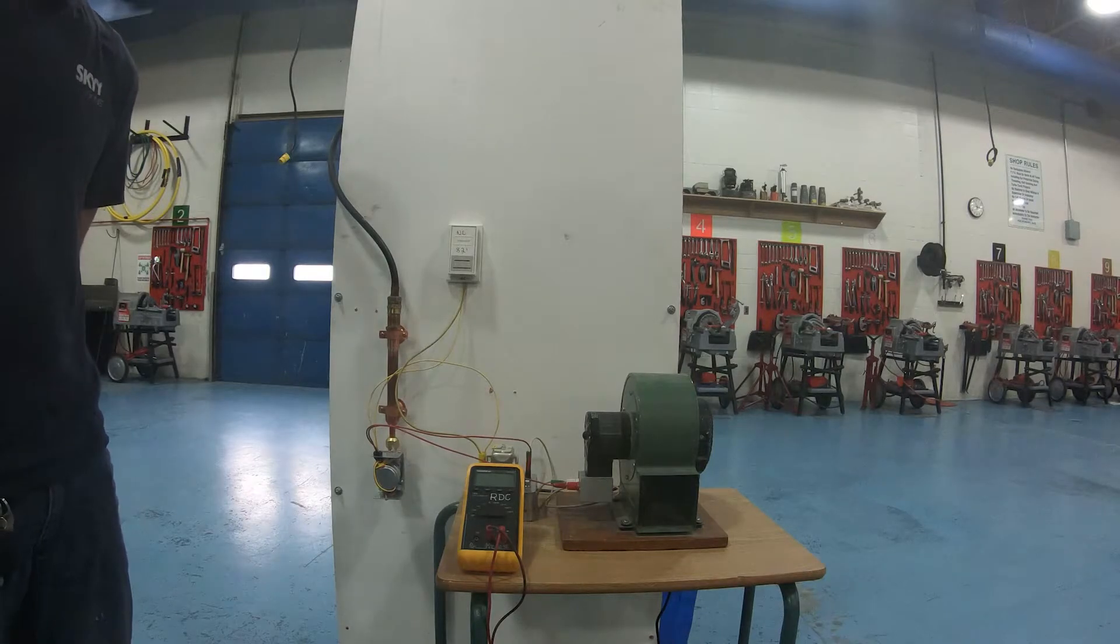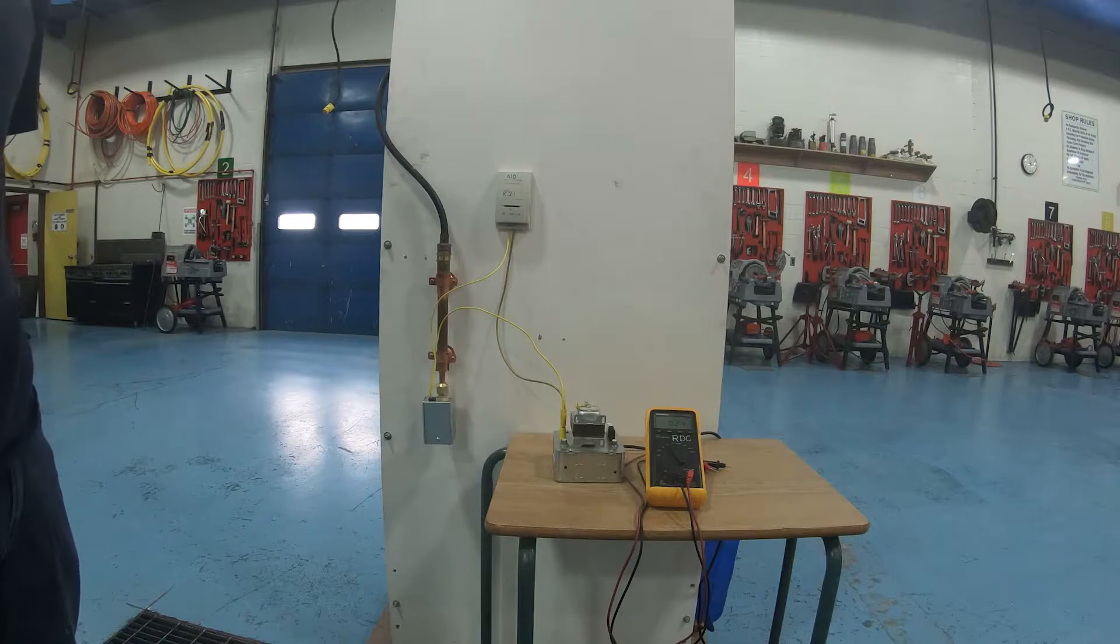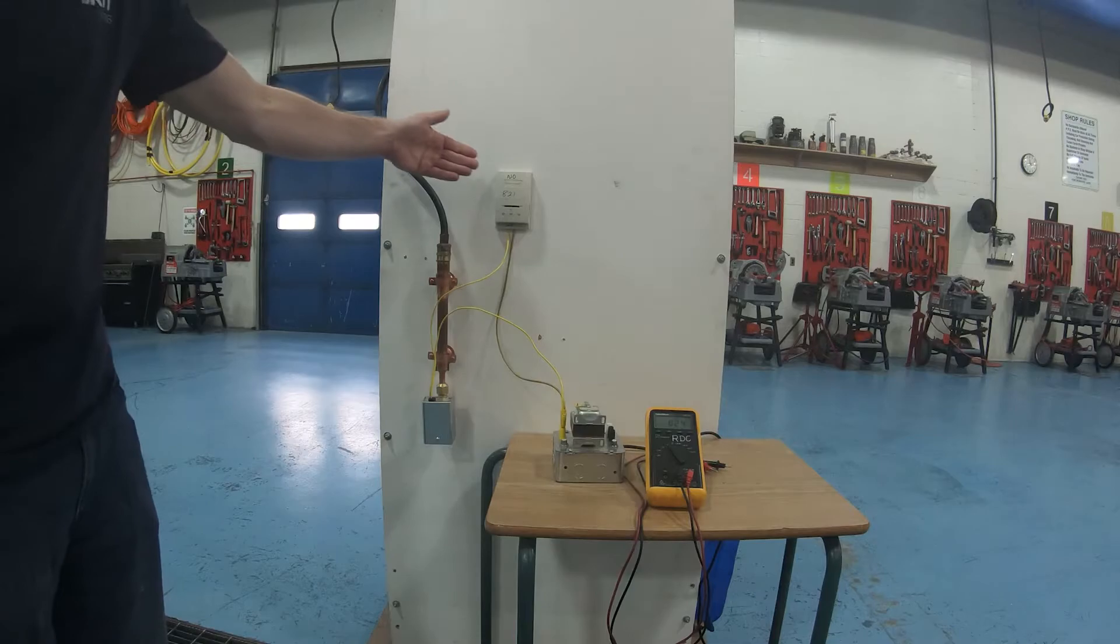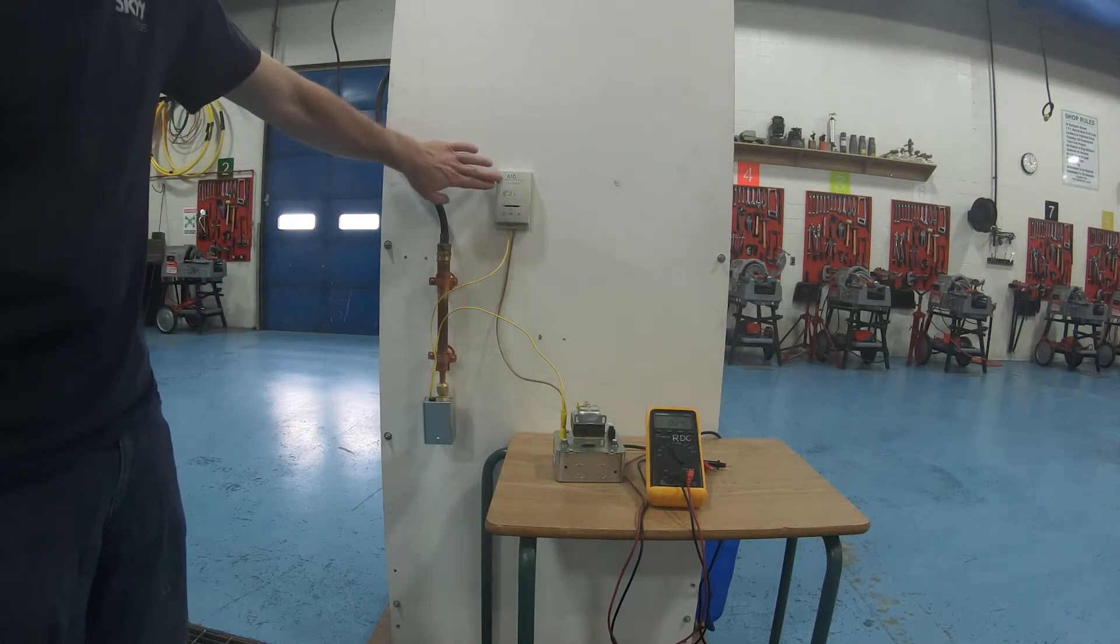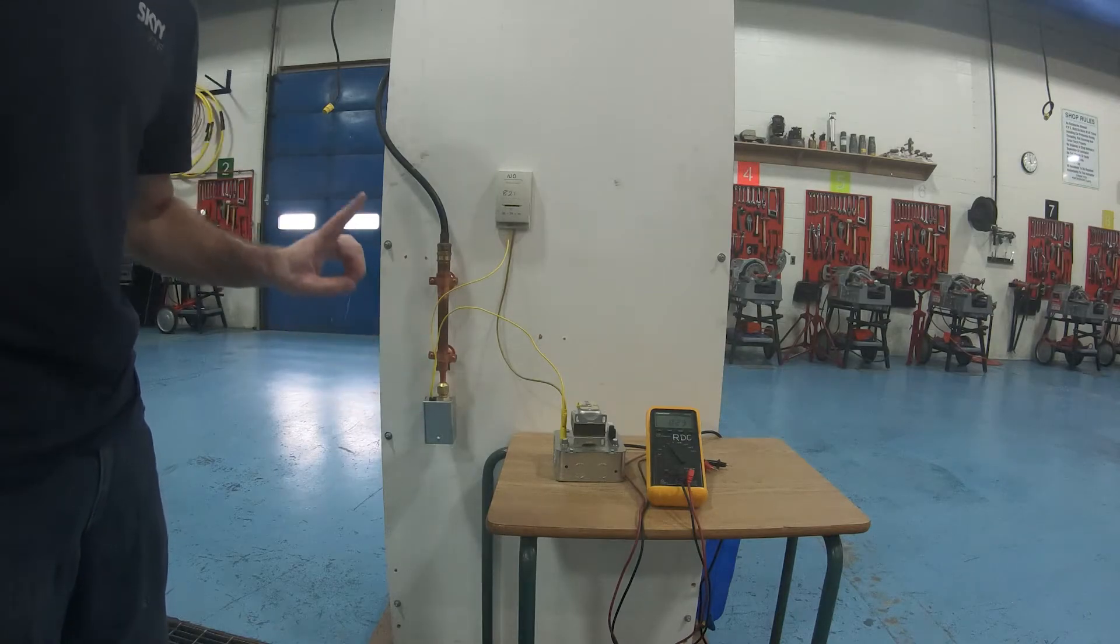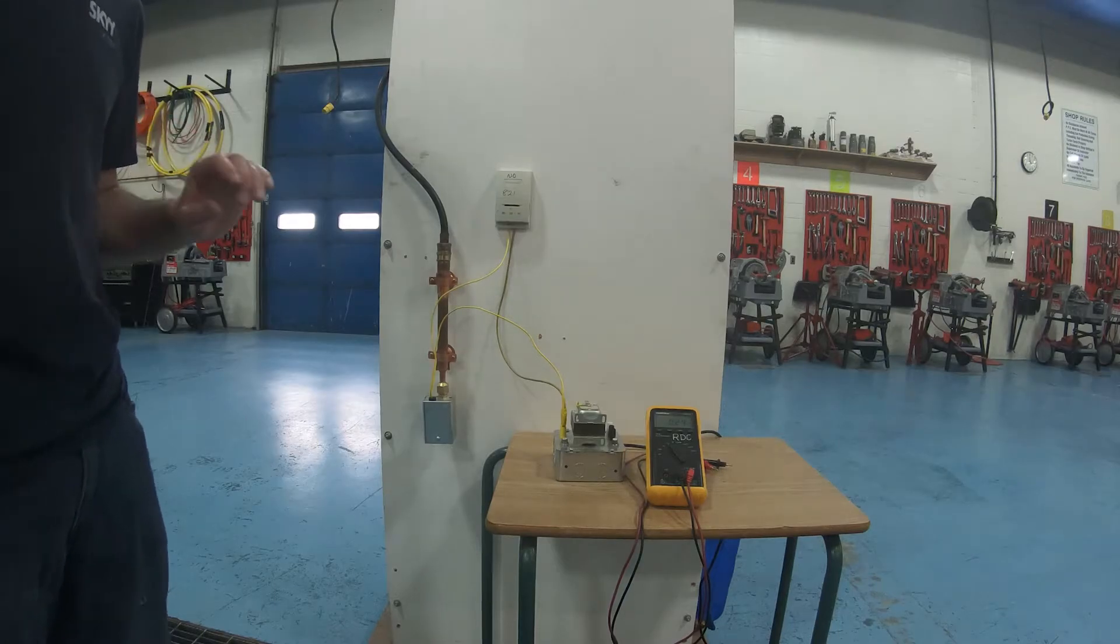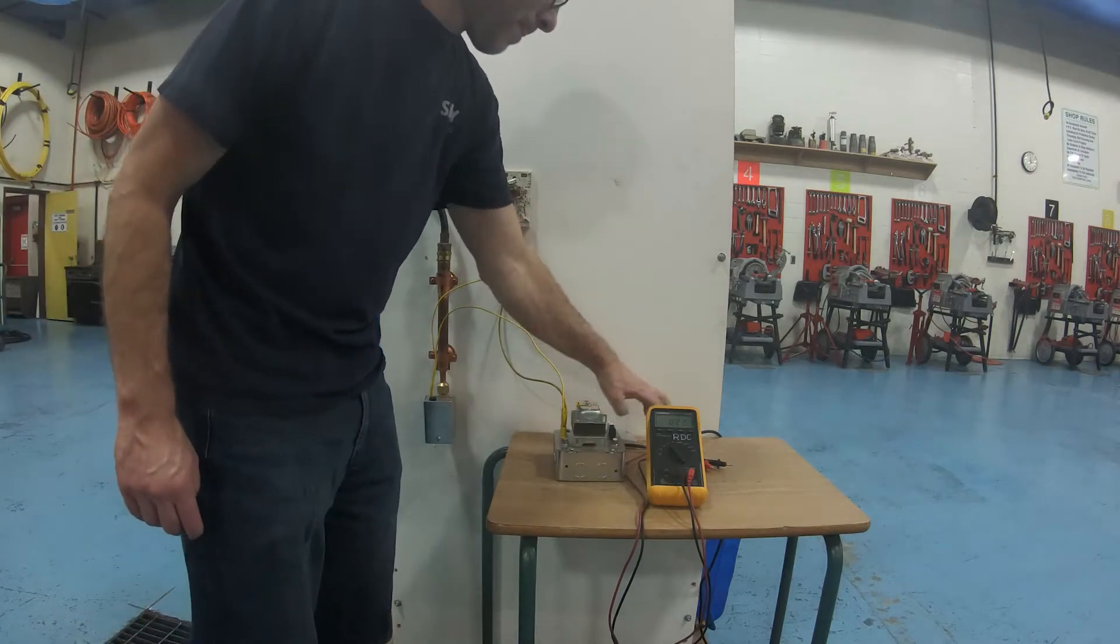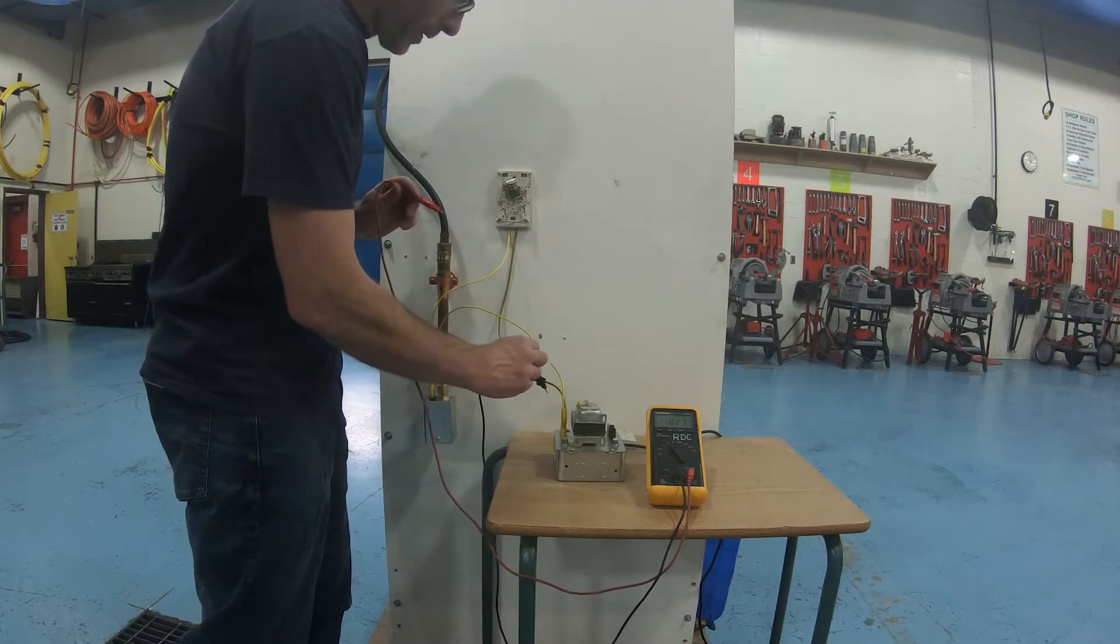Now for the third and final one, this is the normally open zone valve. Now we already looked at the thermostat. The thermostat is reversed of a regular normally closed thermostat, so we call this a normally open thermostat. What is happening here is the zone valve is closed, but it's closed because it has power. Now it's kind of tricky to show you this, so I'm going to have to do it with the electrical meter here.